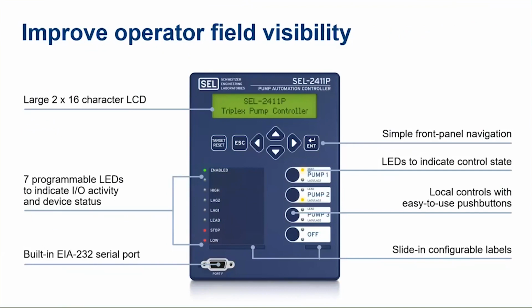When we talk about visibility in the field and being able to make decisions quickly on what's happening, I want to show you a couple of slides with examples. The front of the unit has a 2-line display with big text messages that scroll as alarms populate. We also have LEDs pre-programmed to demonstrate the level at the location, but you can change those to show just the alarms you want to see. The labels are slide-in configurable, so you can print them out and change the text. A lot of customers do this because they want those lights to enunciate based on specific alarms they want operators to key in on when they walk out to the station.